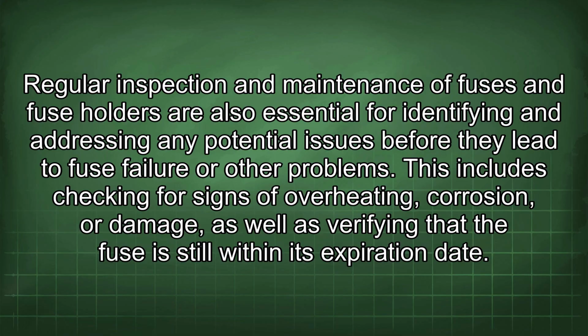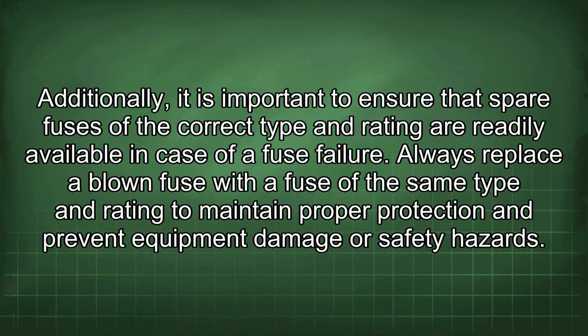This includes checking for signs of overheating, corrosion, or damage, as well as verifying that the fuse is still within its expiration date. Additionally, it is important to ensure that spare fuses of the correct type and rating are readily available in case of a fuse failure. Always replace a blown fuse with a fuse of the same type and rating to maintain proper protection and prevent equipment damage or safety hazards.